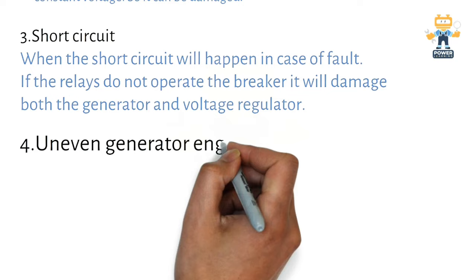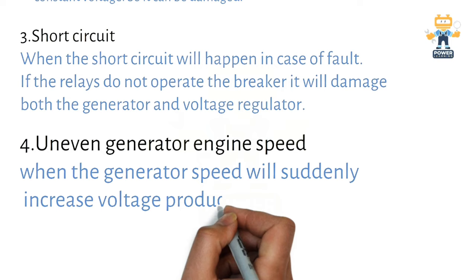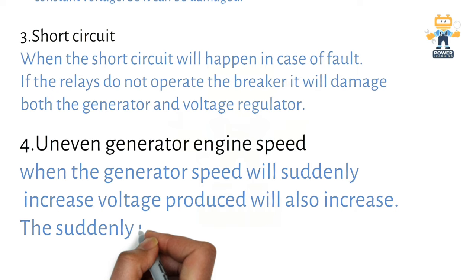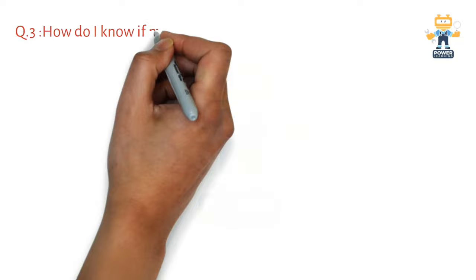Cause number four: Uneven generator engine speed. If your engine is hunting and the engine speed is not stable, this also causes AVR failure. When the generator speed suddenly increases, voltage produced will also increase. The suddenly increased voltage will damage the AVR.